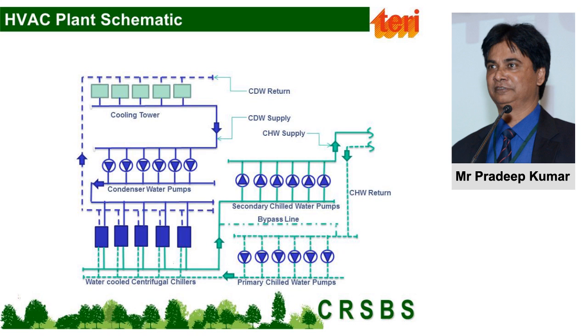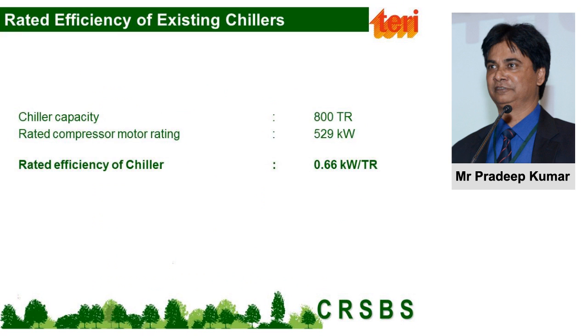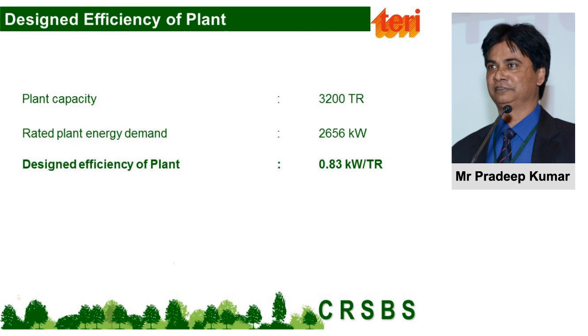When we started our work, first we calculated the rated efficiency at full load at what we call the Indian duty condition operating points. We found the chiller was somewhere around 0.66 kilowatt per TR, and the plant, meaning the chiller plus auxiliary, somewhere around 0.83. So the design was not bad. Generally, you can say it's 0.6, even if we take what is recommended by ECBC, it is somewhere close.